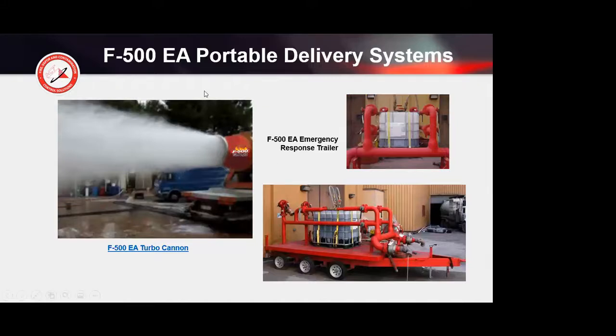These are just also showing some portable delivery systems. This is something we promote with the power industry, because if you have a transformer and you have a fixed system and your transformer explodes, and it takes out some of the sprinkler system, you may have to have a manual attack. So some of our customers are using trailers like this that are designed with monitors, say 250 up to 500 gallons per minute. Others are using the F500 turbo cannon.